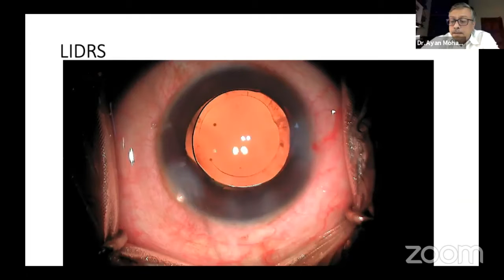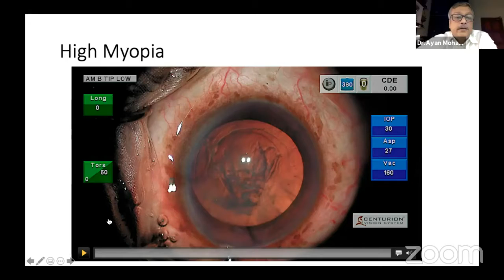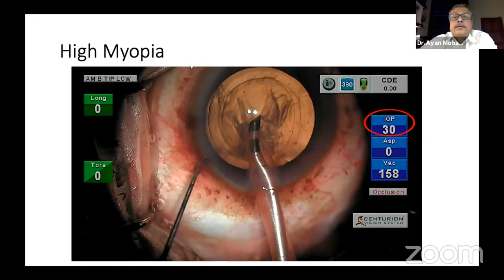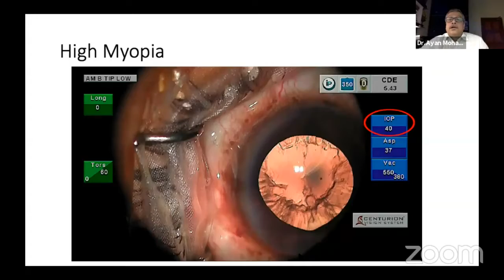Here you can see again the IOP, if you notice, is 30. In this particular case, you see I'm entering the anterior chamber with very little fluctuation of the iris pupil diameter. These are the benefits of active fluidics, wherein you can control the amount of fluid that goes inside the eye. And in a gravity-based system, your bottle height should not exceed 60 to 70 centimeter from the ground. Here you can see again, I'm taking out my phaco probe suddenly, and there is a PVD that has been induced.